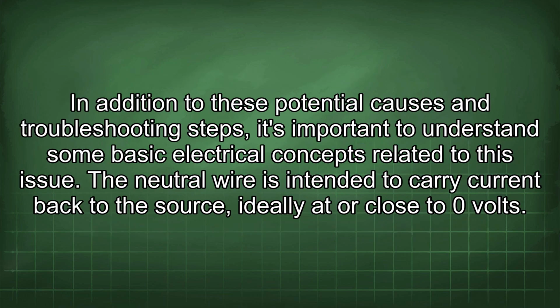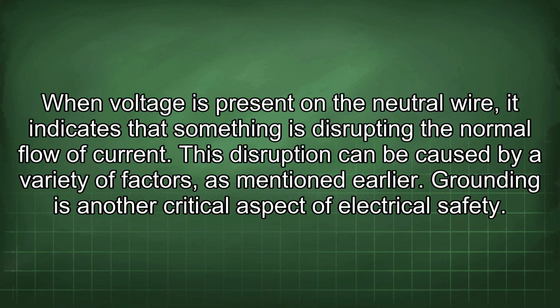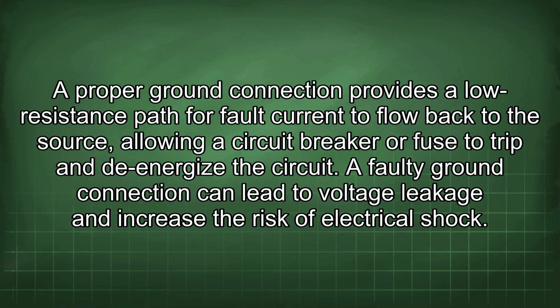In addition to these potential causes and troubleshooting steps, it's important to understand some basic electrical concepts related to this issue. The neutral wire is intended to carry current back to the source, ideally at or close to 0 volts. When voltage is present on the neutral wire, it indicates that something is disrupting the normal flow of current. This disruption can be caused by a variety of factors, as mentioned earlier. Grounding is another critical aspect of electrical safety. A proper ground connection provides a low resistance path for fault current to flow back to the source, allowing a circuit breaker or fuse to trip and de-energize the circuit. A faulty ground connection can lead to voltage leakage and increase the risk of electrical shock.